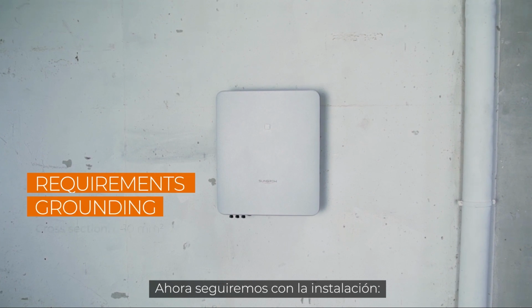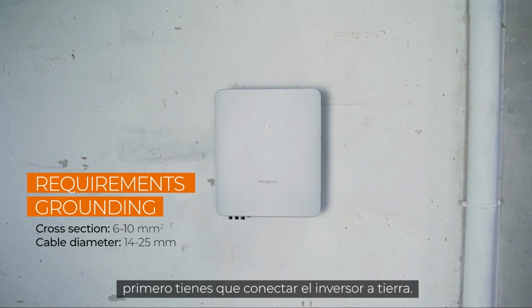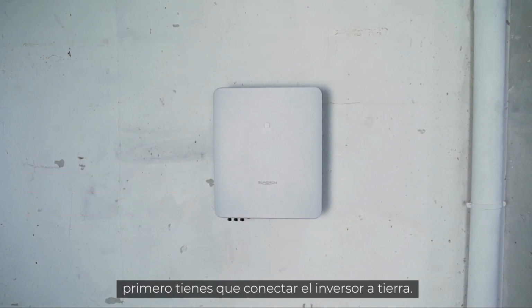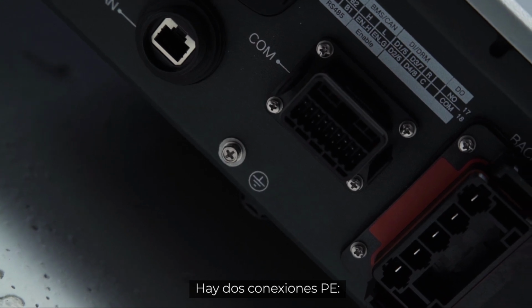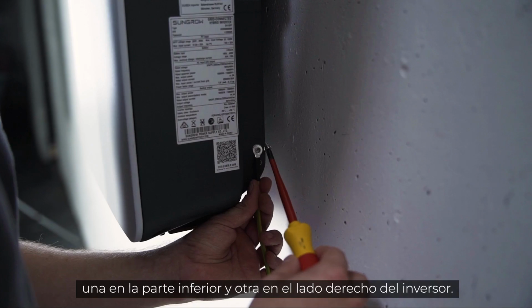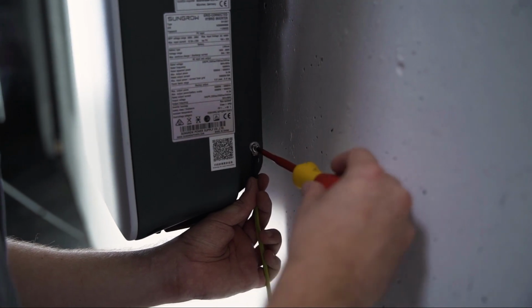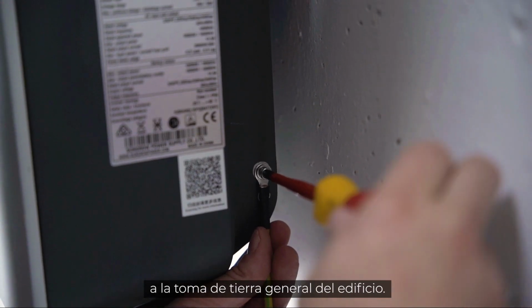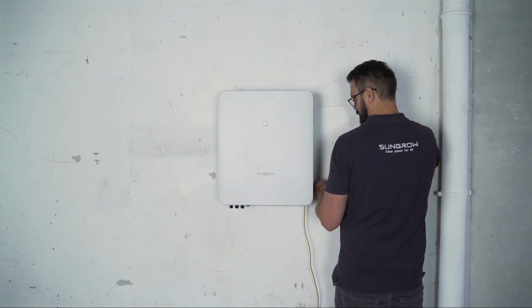Now let's continue with the installation. In the first step, you have to connect the inverter to ground. There are two PE connections, one at the bottom and one on the right side of the inverter. At least one of them has to be connected to the general grounding of the house.